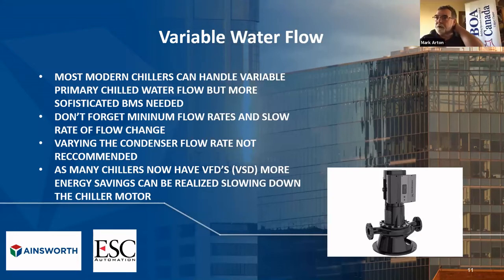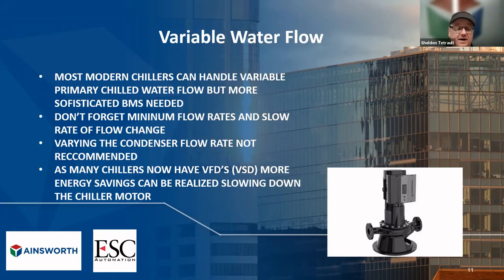There is another question if you want to take a crack at it. Sure. So Godfrey is asking, how can we address or limit any occurrence of chiller surges? So chiller surges, although it can be quite a few different things, it's often two things. Either air in your chiller, so you have a reduced condenser capacity, or too hot of water or not enough water. So three things from the cooling tower.